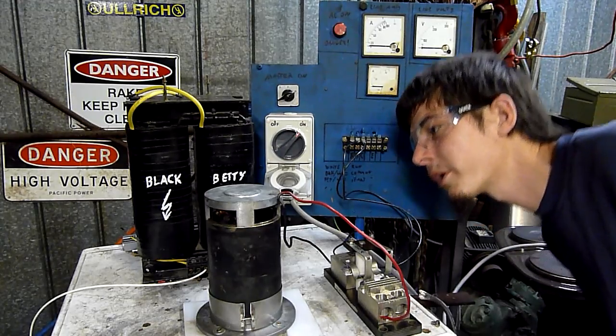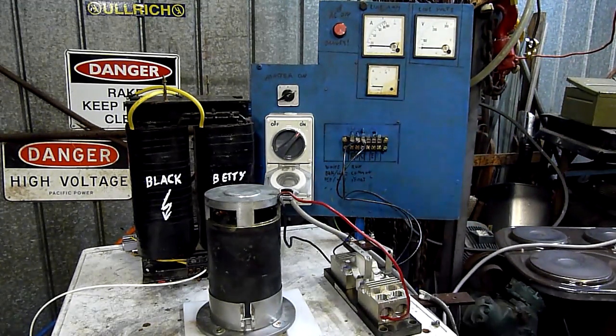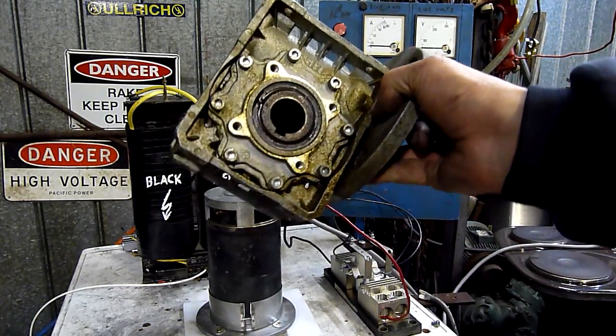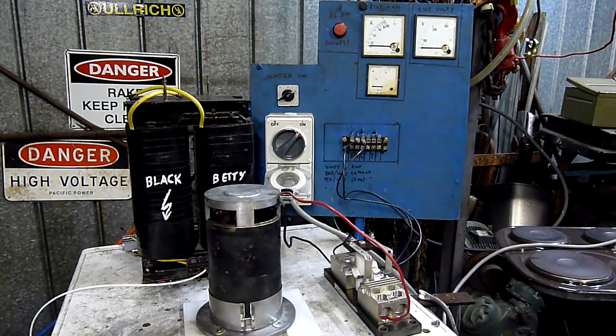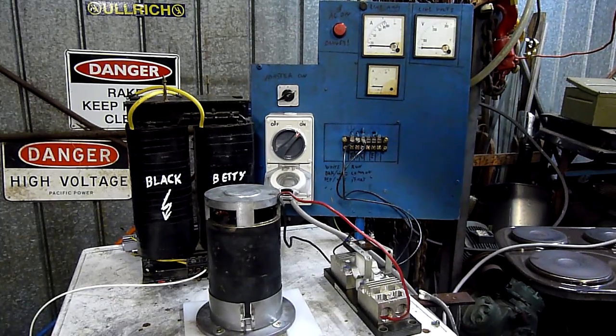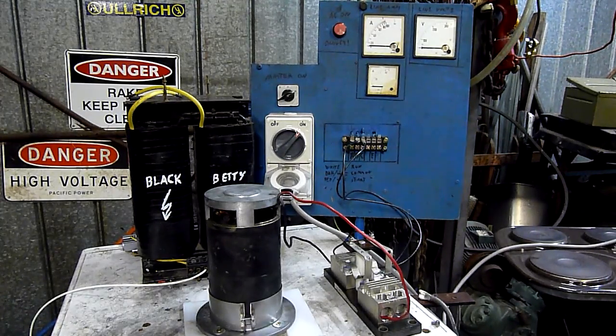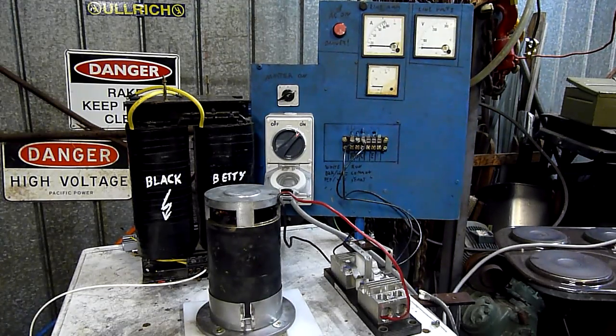This motor has been oil damaged — the speed reducer that was attached to it leaked down inside and caused some serious arcing and burning. That's what's left of the speed reducer; it's an absolute mess and the motor has suffered serious damage, that's why I'm killing it. I've also got several others which are in bad shape and several which are in good shape, and I'm not going to blow those up. Trust me, it's worth it.